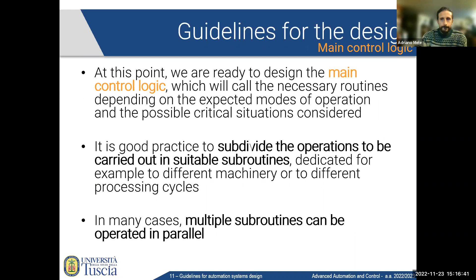Another aspect that needs to be considered is the possibility of power failures. If the PLC is left without power supply during a machining process, it may be useful to preserve the state of some variables, as we've already discussed. Maybe you're in the middle of some operation and power goes off for whatever reason. When you start again, you need to reset your plant, and that can take a lot of time and effort. So in some cases, it's good to analyze whether specific variables should be preserved in order to avoid a long restoring time after a shutdown.